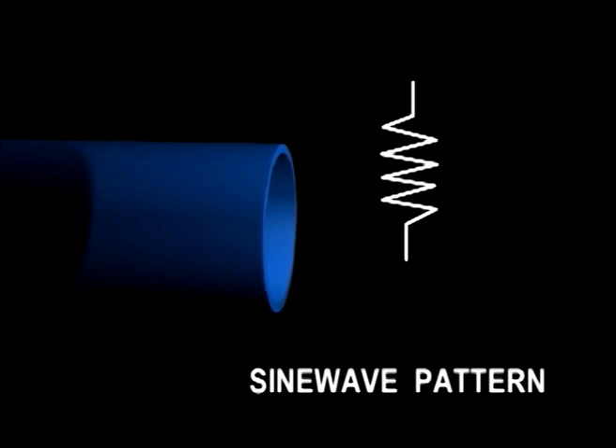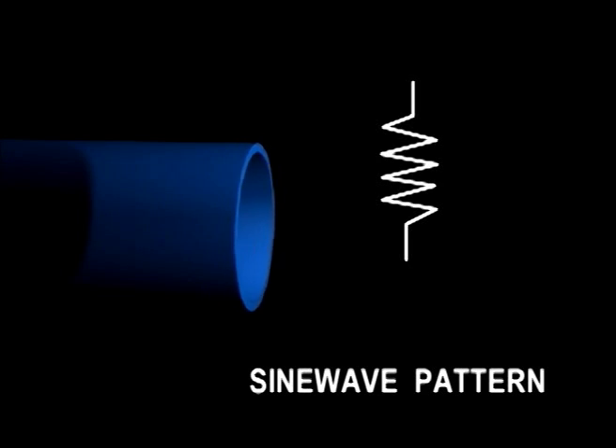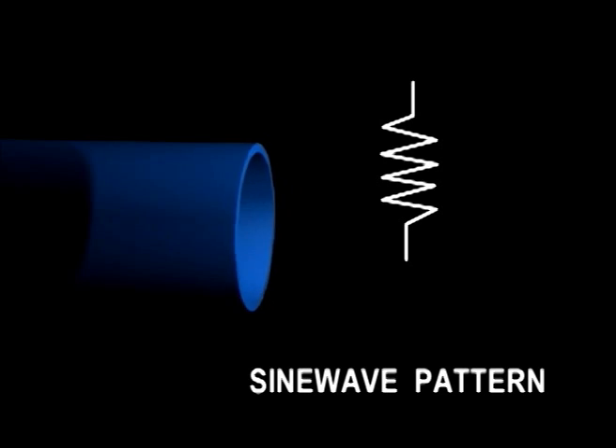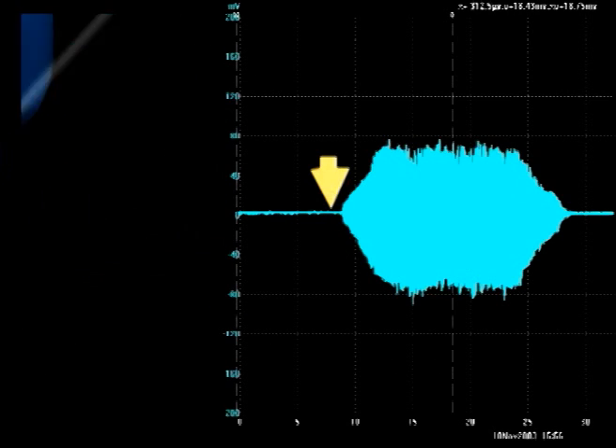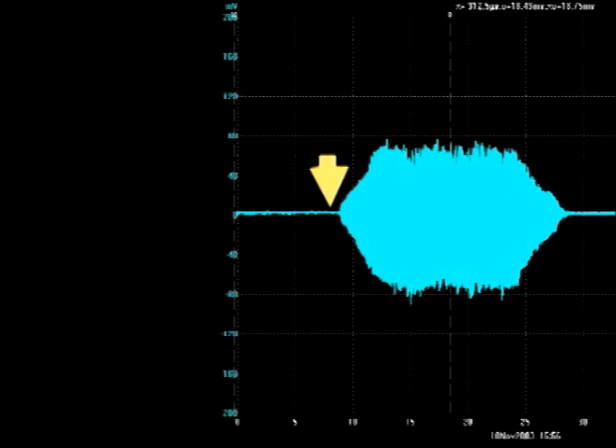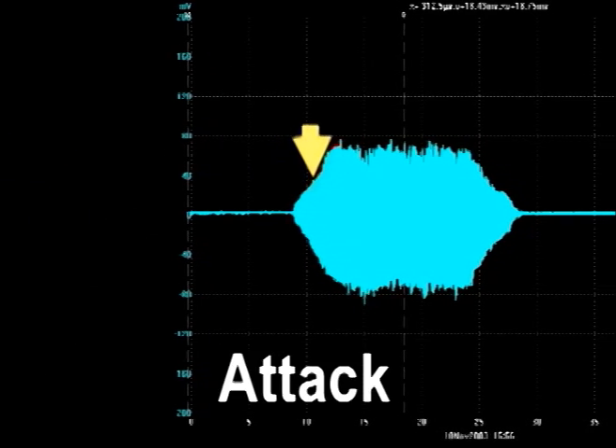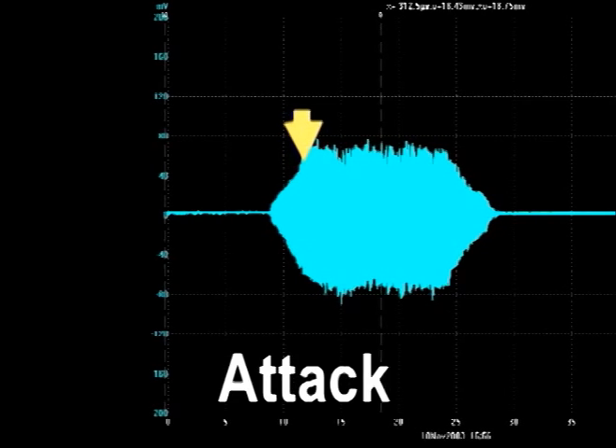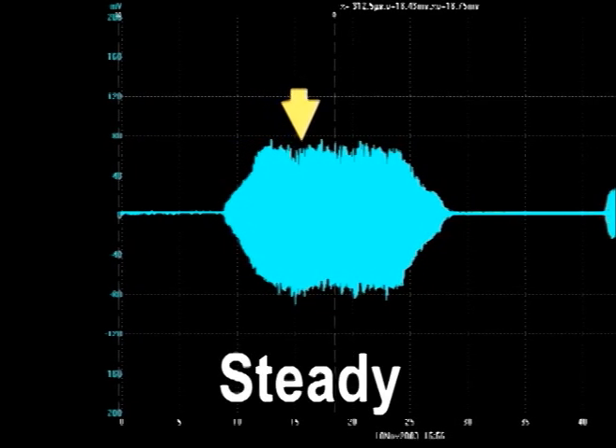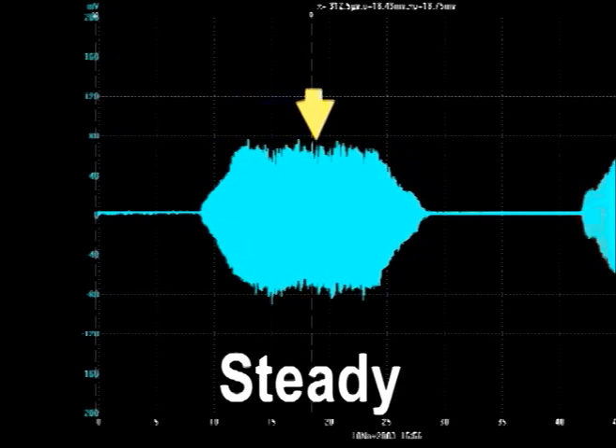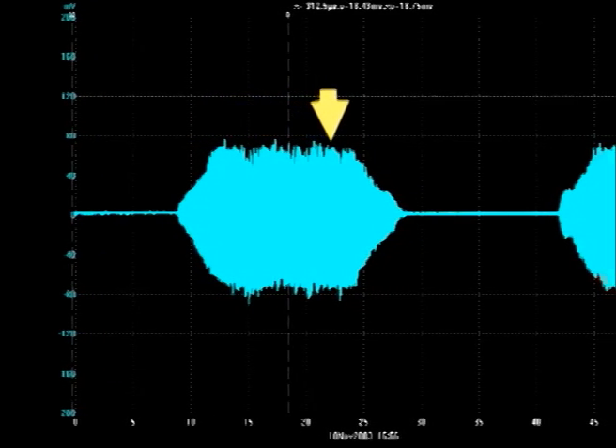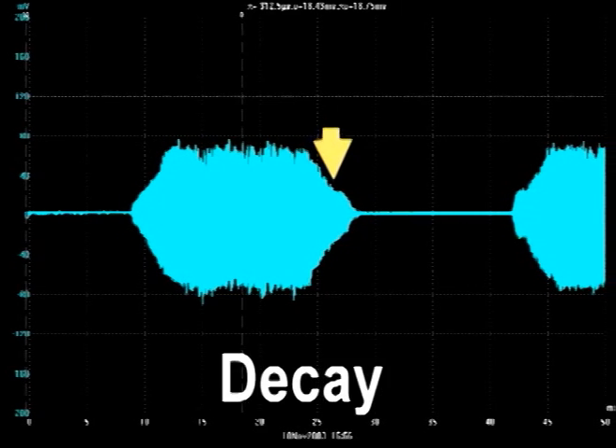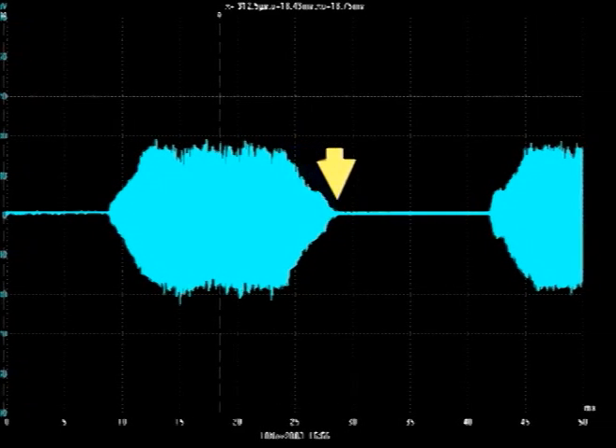A standard pulse will make a phaco tip oscillate around a center position following a sine wave pattern. Stroke will grow during the initial portion or attack zone, remain constant during the steady zone, and exhibit an after-pulse ringing, creating a decay zone.